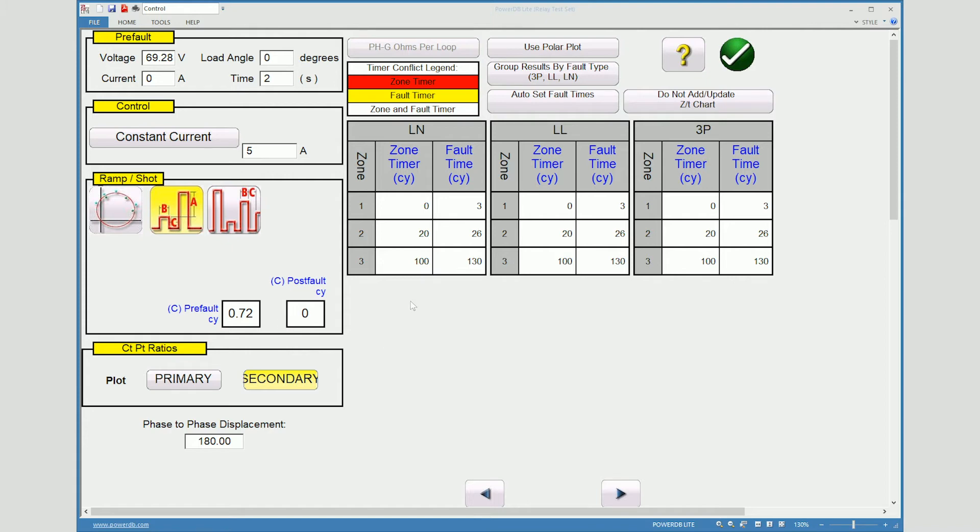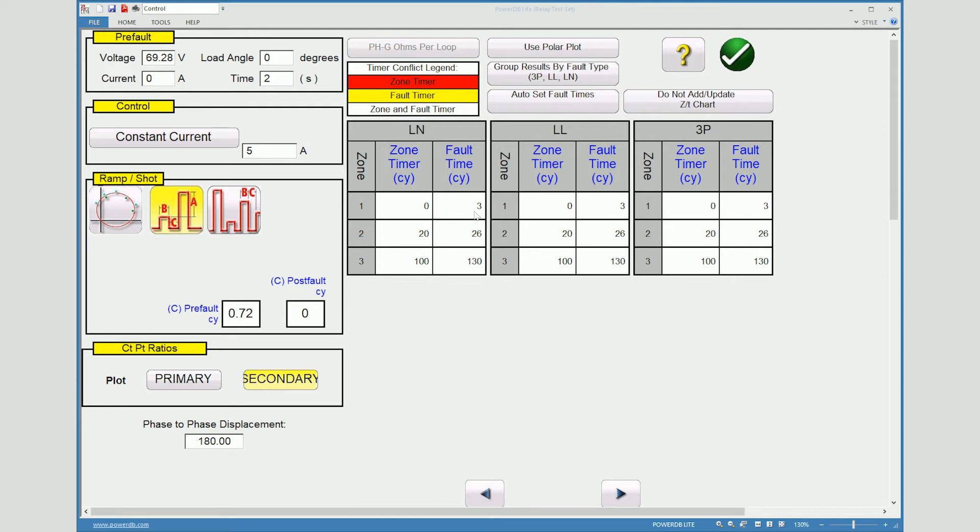Now you view over here you will see the zone timers. And this came from the information from the settings that I did import into the test. You will notice that it has for zone one it has zero so there is no inherent time delay here. But we're actually going to pulse this to the fault for a little bit over zero because you have to have some time. You cannot just turn on the test.